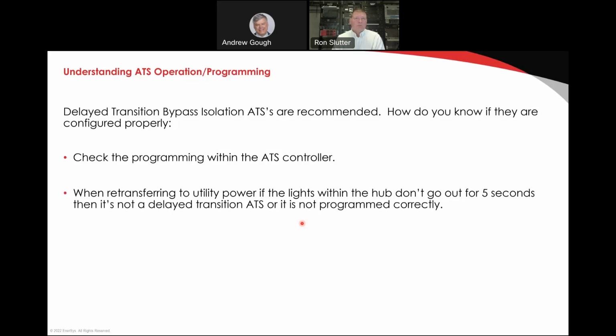The person responsible for maintaining an ATS needs to be very familiar with it. I always recommend having OEM certified technicians work on ATSs. Typically in the industry, we see generator people working on ATSs, and they don't always get the subtleties of the requirements within an ATS. They're very good with generators. However, the ATS does not always match the manufacturer of the generator. So you could have a Cummins generator and you could have an ASCO ATS.